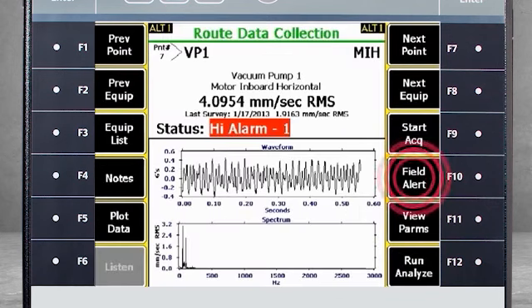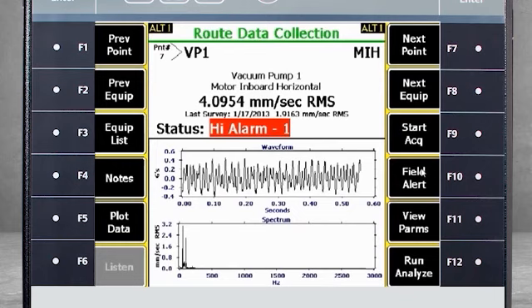F10 Field Alert allows you to flag measurements from the field for priority back in the office. For example, if you have 50 machines on your route and 10 measurement points per machine, you'll be collecting 500 points. But if you notice a significant problem on one machine that requires immediate attention, add a field alert. Back in the office when the data is downloaded to the software, the analyst can filter data for field alerts and analyze that data first.